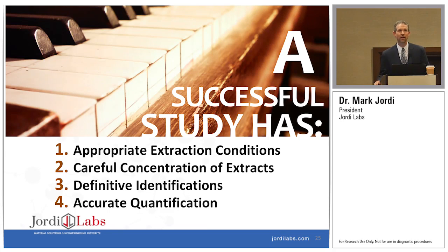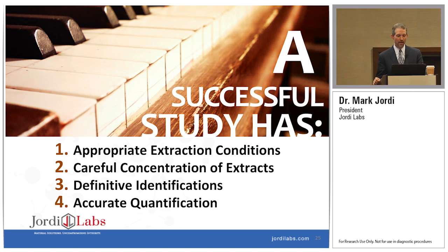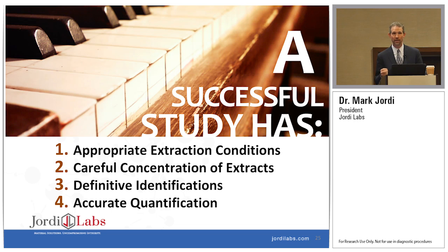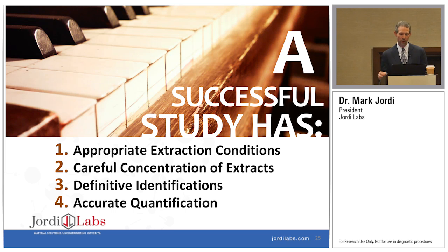In conclusion, for a successful E&L study it's very important that: number one, we pick appropriate extraction conditions that mirror the actual use conditions for the device or packaging; number two, we are very careful in how we treat those extracts, because that's often overlooked and in doing so we may be losing the very things we're trying to characterize; number three, we need to get to definitive identifications, which is really where the QTOF instruments have been so valuable; and lastly, we need to do accurate quantitation. Getting to values is not enough — we need accurate values so that when we put those into our toxicological models, we can be confident that we will have an actually safe device or packaging system. Thank you very much.